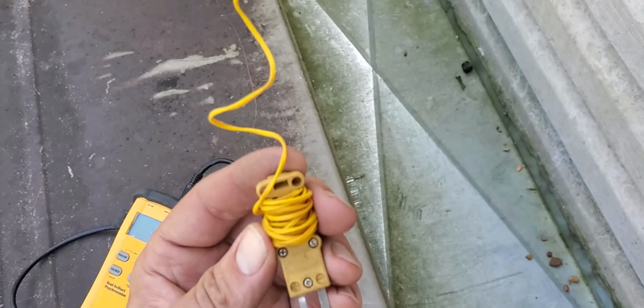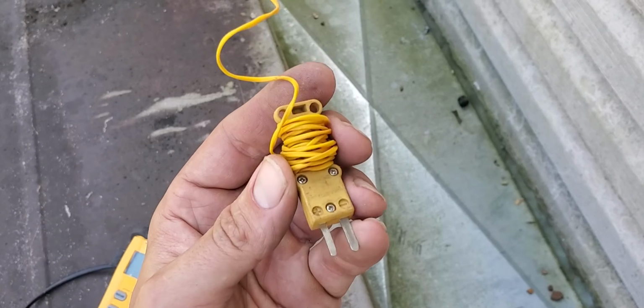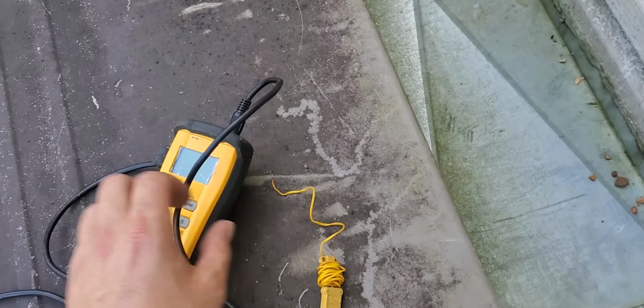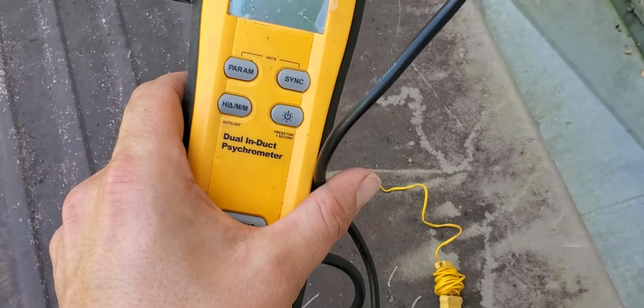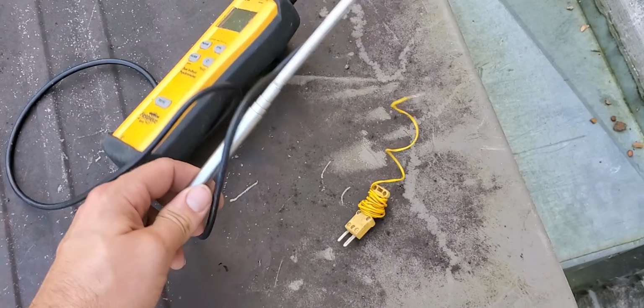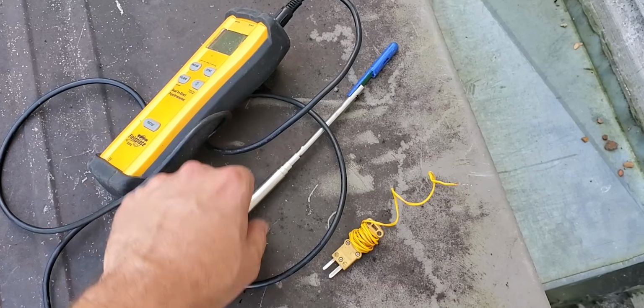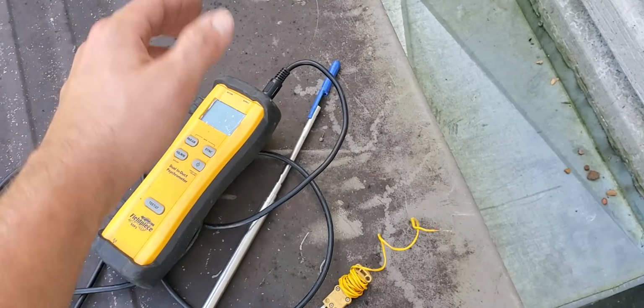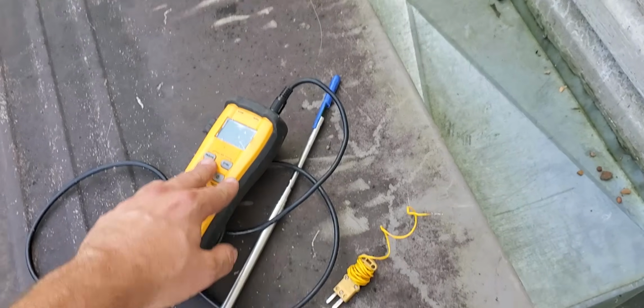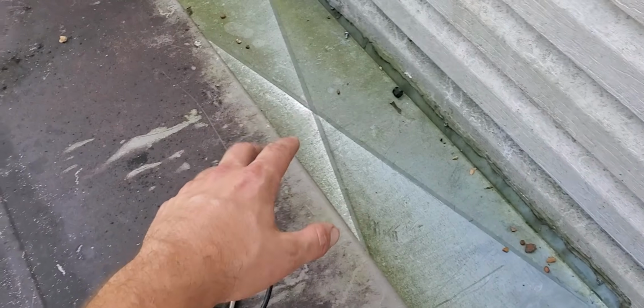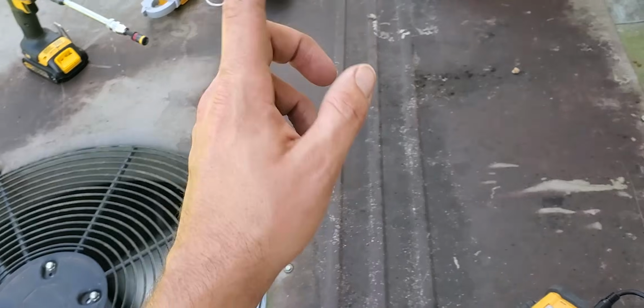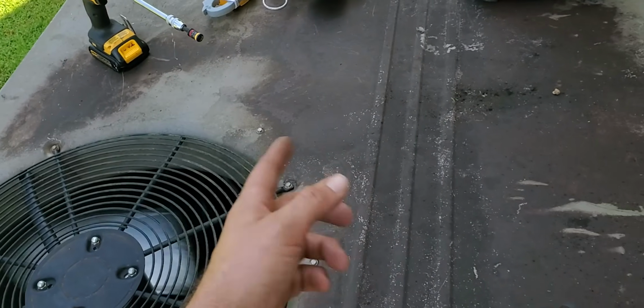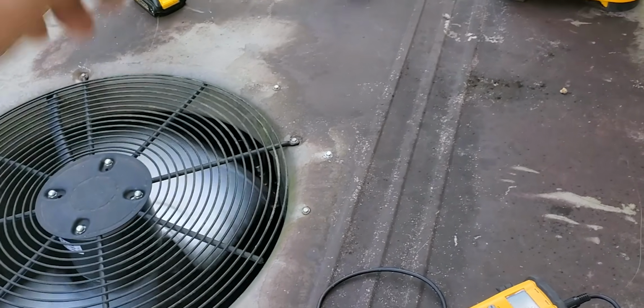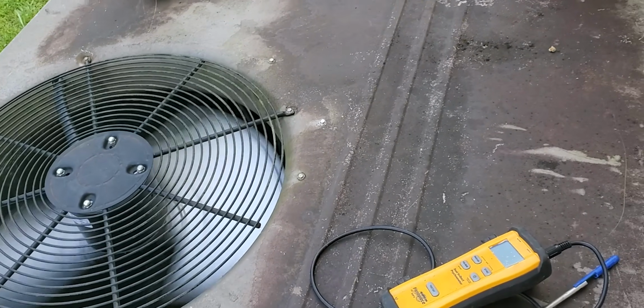So you can use a little temperature sensor here that plugs right into the FieldPiece meter, or you can use a dual end duct psychrometer. These probes have seen better days. I actually broke this one, and the other one I broke, and I've got to get new ones, so I'm going to order those. But check your temperature split while you're checking your liquid levels in each side of the coil, the evaporator coil and the condenser coil. Make sure you check the temperature split.